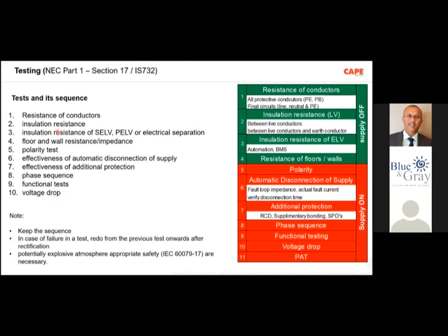There are 10 tests. Now, with these 10 tests, you have to be sure that we are supposed to follow this sequence. For the initial verification, meaning you have a new electrical installation, or a modified electrical installation, or an added electrical installation, before putting it into service you are supposed to do all the tests. For a periodic test, you don't need to follow all the tests. You can excuse some of them, but again, that depends upon your application. What you should keep in mind is that you are supposed to keep the sequence. In case of failure in any of the tests, you have to rectify the defect and redo the previous test onwards after rectification.